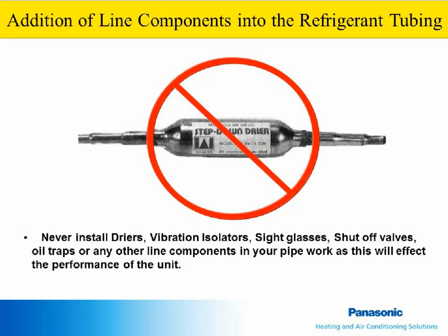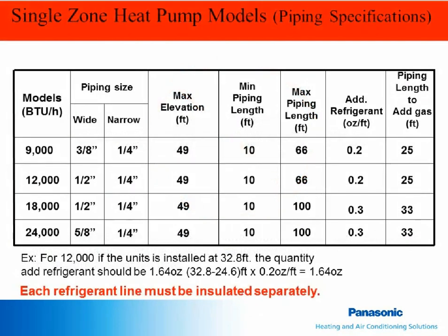Never install dryers, vibration isolators, sight glasses, shut-off valves, or oil traps in the line set. If there is a service issue and the system needs to be cleaned, dryers can temporarily be used, and this will be talked about more in the service course. All units have piping length and elevation limitations. The installation instructions, which are included in the box, have these limits for your specific unit.